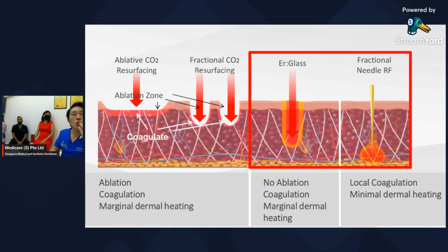So, microneedling RF has more or less successfully managed to achieve that goal by penetrating. The needle penetrates to a preset depth and emits RF heating at the deeper layer of the skin, and you only get an epidermal puncture wound. The needle can be insulated, so you achieve a candlestick-like effect, with most of the energy being delivered to the deeper parts of the skin, while the surface of the skin remains cool. Okay, so that's the theory.